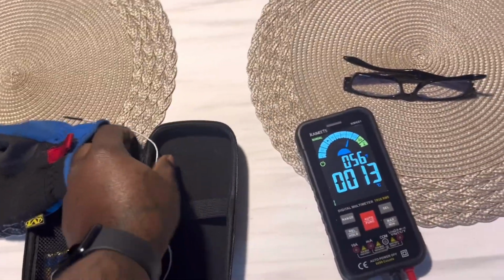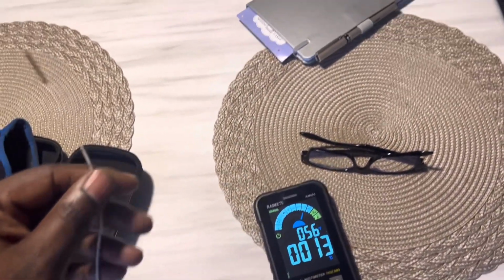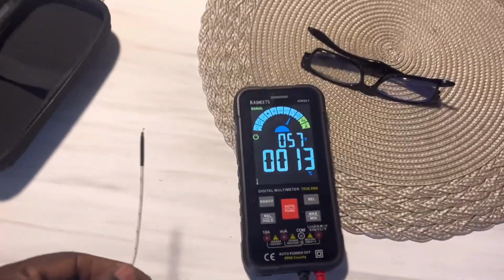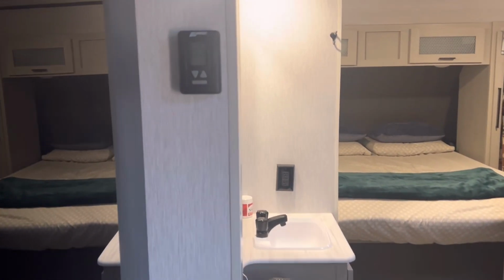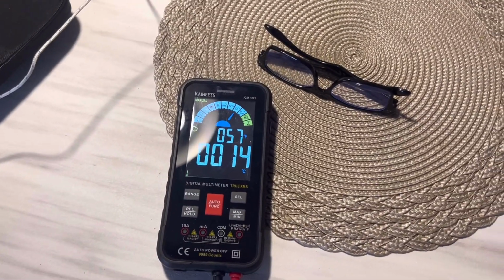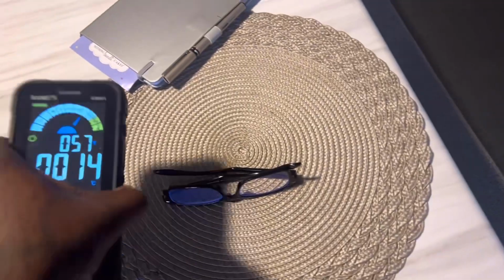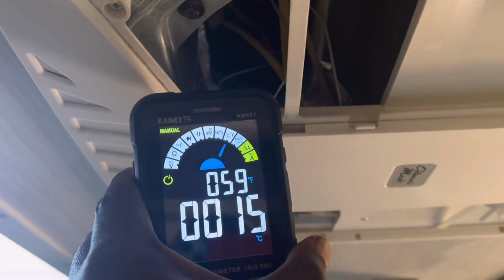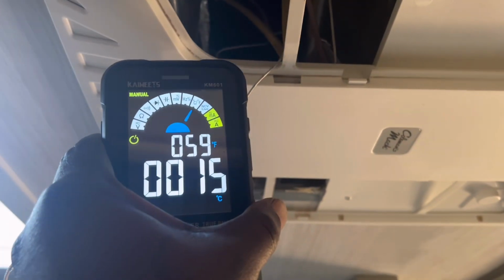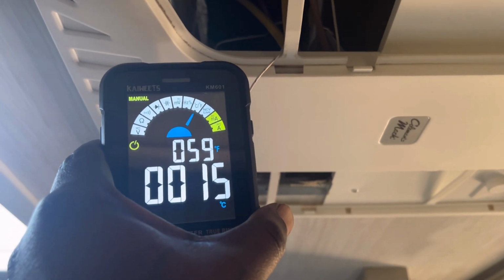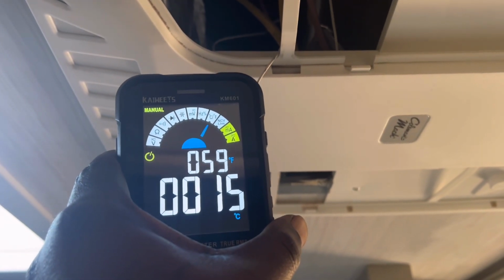All right. You're not supposed to use those infrared temperatures to do this. They want you to use a real thermometer or electronic thermometer. As you can see, our thermostat is saying 65, and our ambient temperature here in the slide room is climbing. Currently it's at 57. These measurements need to be taken at the intake. So at my intake, the actual air being drawn into the system, I'm getting closer to what my thermostat is reading, and I'm about at 60 degrees.